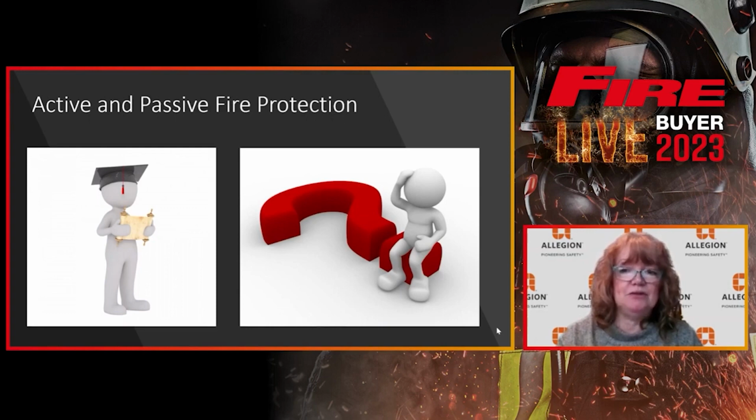Passive fire protection is in use daily and may be used multiple times within a day and thousands of times within a year. With no maintenance in place, the hardware supplied may not perform as it did when new. Doors may become difficult to open or slam shut, causing inconvenience and potential risk to those using them. Quite often when this happens, door closers tend to be disengaged, or doors wedged open, with people not understanding the importance of this protection and what role it plays in the event of a fire.